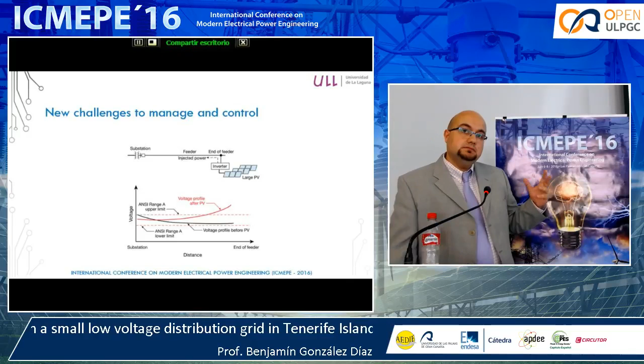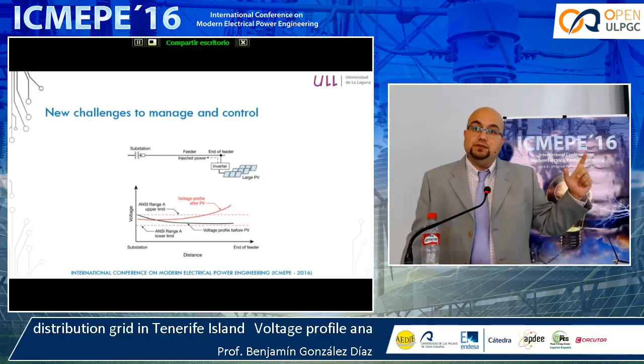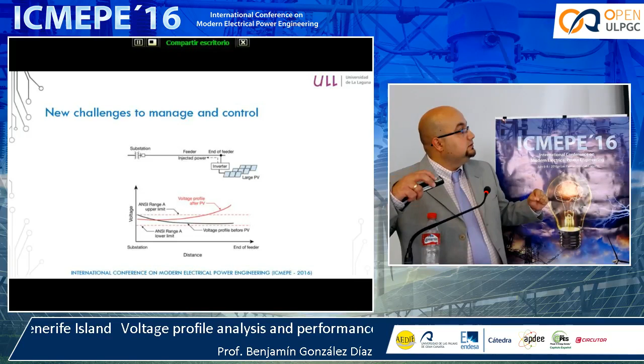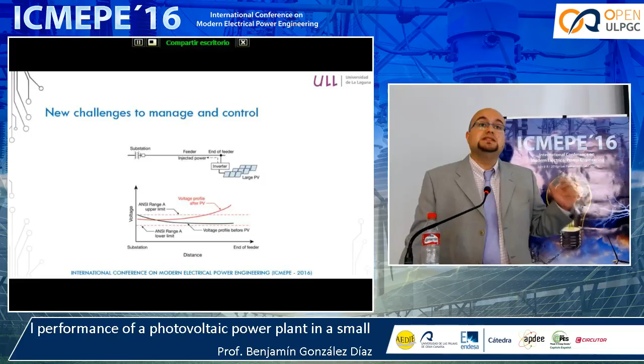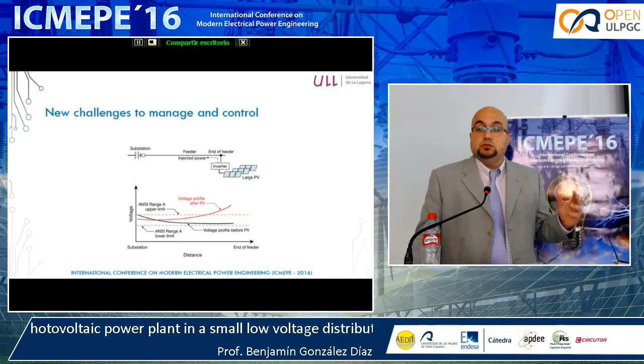But what happens when we put a photovoltaic power plant at the end of the feeder, near the end of the line? We see that the voltage profile rises, and sometimes goes higher than the upper limit of 7% of the nominal voltage. This is a problem for keeping the system working, because all devices are designed to operate between two limits, plus and minus 7%.